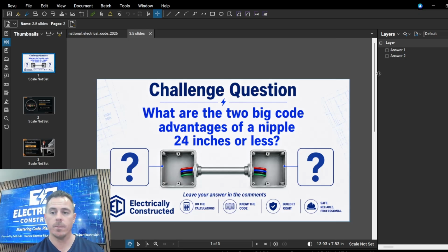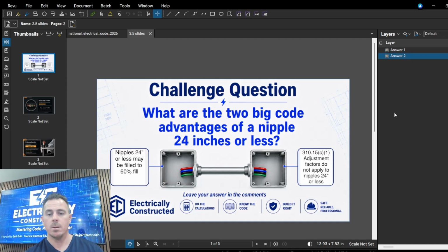All right, and the first answer for that would be nipples 24 inches or less may be filled to 60% fill. And the other answer, 310.15C1 adjustment factors do not apply to nipples 24 inches or less. So if you watched that video, then those answers should have come pretty easy for you.